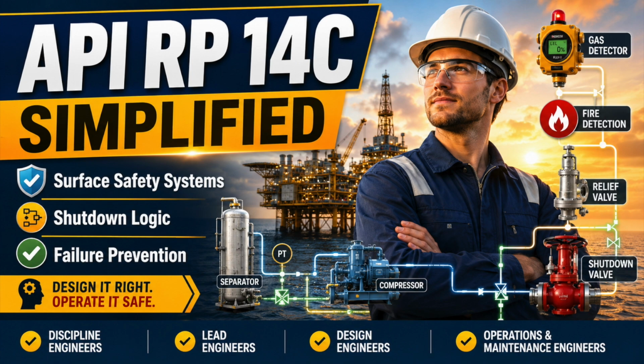Containment must direct liquid hydrocarbons towards safe drainage and collection. Sumps must be treated as hydrocarbon equipment, not forgotten utility pits. Drain systems must prevent gas migration. The final destination of every leak must not become the least protected part of the facility. The shutdown system is also only as reliable as its utilities.